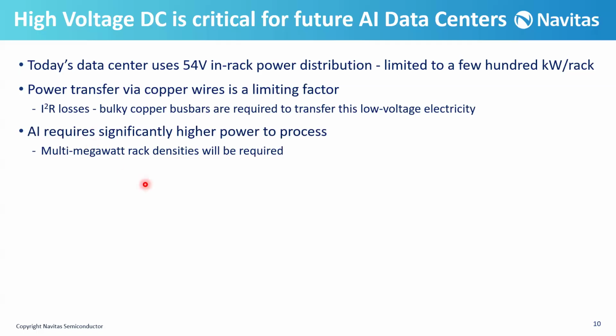Now, AI requires significantly higher power to process. And it means that we need higher power. So if we have a constant voltage, we need higher current. And again, we have higher power loss. So in other words, we need to increase the voltage instead of increasing the current. And this is the reason that the new architecture is required: plus minus 400 volt to 800 volt DC.